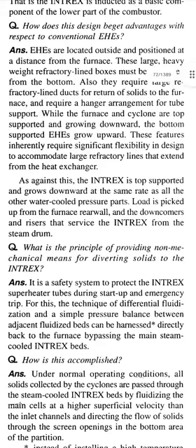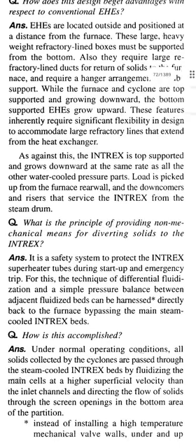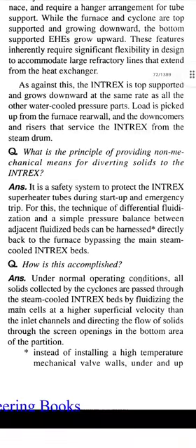As against this, the Intrex is top supported and grows downward at the same rate as all the other water cooled pressure parts. Load is picked up from the furnace rear wall, and the downcomers or risers that service the Intrex from the steam drum. The next question. What is the principle of providing non-mechanical means for diverting solids to the Intrex?